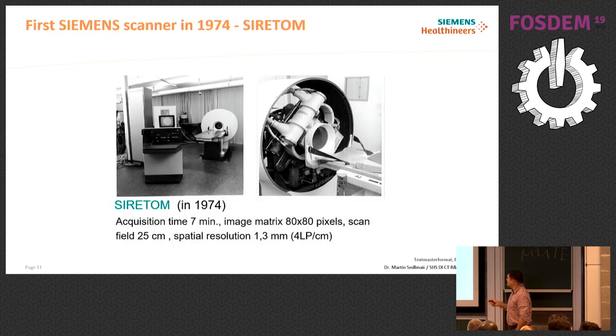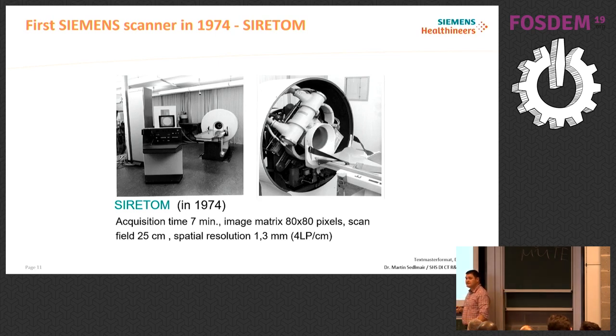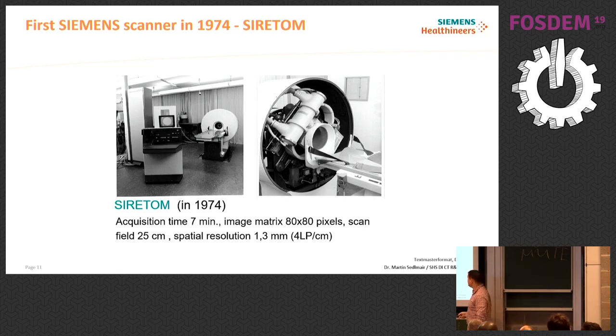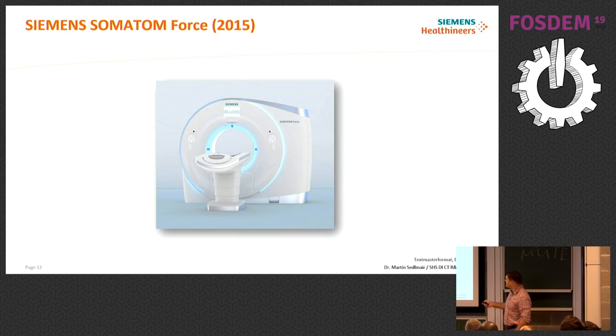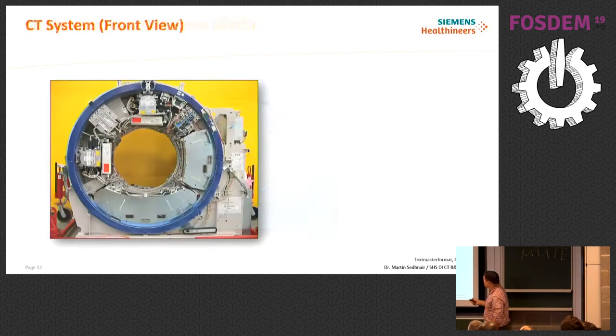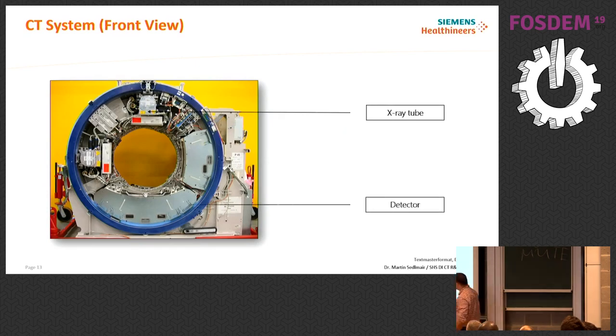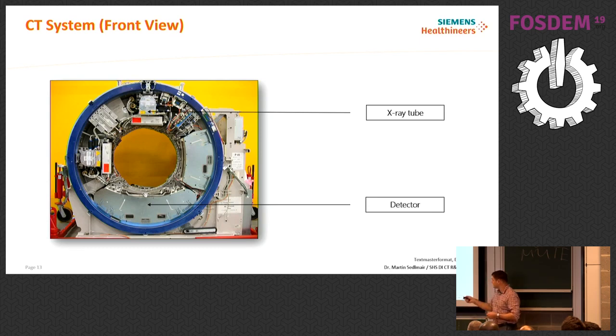In 1974, Siemens released the first publicly available CT scanner. It was only for the head, and the acquisition time was seven minutes. The modern system allows you to put in the whole body. Inside you have the X-ray source and a detector — the most expensive components, around 50 to 80,000 euros for these two components alone. You also need a high voltage, a cooling system, electronics, and power transmission.